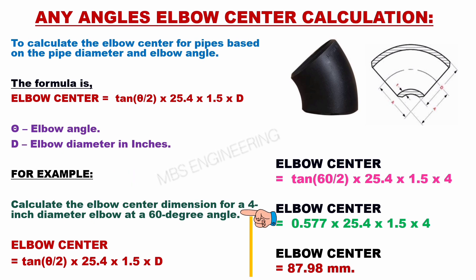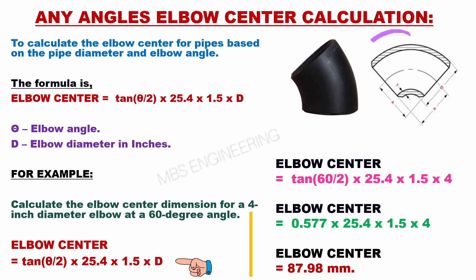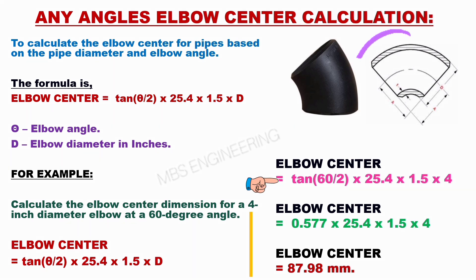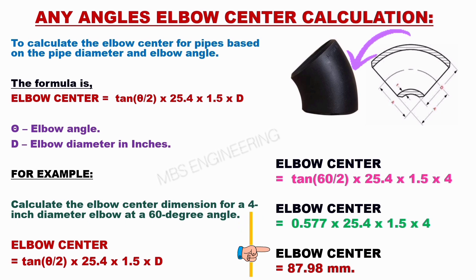Calculate the elbow center dimension for a 4-inch diameter elbow at a 60-degree angle. Applying the formula: Elbow Center = tan(60/2) × 25.4 × 1.5 × 4 = tan(30°) × 25.4 × 1.5 × 4 = 0.577 × 25.4 × 1.5 × 4. The elbow center for a 60-degree angle is 87.98 millimeters.